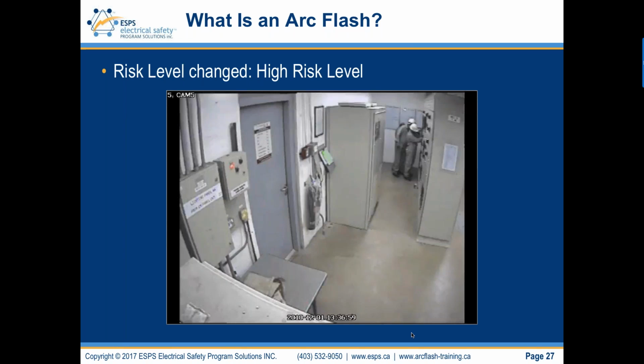And if there was a permit, then an arc flash and shock risk assessment would have been completed to establish boundaries and PPE. Overriding the arc flash and shock risk assessment would have been an analytical risk assessment procedure to ensure that the risk level, in this case low, medium, or high, was managed to lower-medium by applying the hierarchy of controls. And all of those workers shouldn't have been there. The primary worker should have had arc flash and shock PPE on. There should have been an electrical work zone with red danger tape and tags to keep them out.